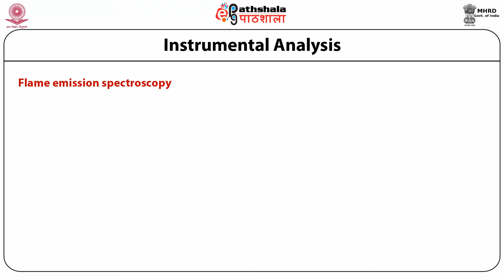Another technique based on emission is flame emission spectroscopy. Flame photometry or spectroscopy is based on the measurement of the intensity of the light emitted when a metal is introduced into a flame. The wavelength of the color tells us what the element is, and the color's intensity tells us how much of the element is present. In early experiments, the visible color of the flame was used to confirm the presence of certain elements in the sample, particularly alkali metals and alkaline earth metals.